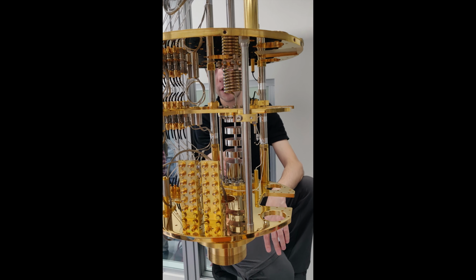This is another phenomenon unique to our universe: when the helium-3 from the rich phase passes through the phase boundary, it cannot simply pass through. It must absorb heat from somewhere, and it absorbs it from the unit bottom, which isn't just a plate - it has very fancy fins inside, covered with sintered silver to increase the surface area. That's a quantum phenomenon - when it passes, it needs energy, so it takes it from there, and the heat goes from there into the helium as it passes the phase boundary.